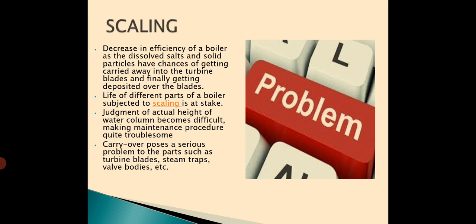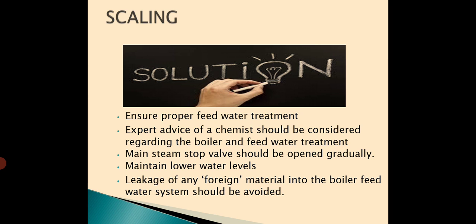Let us see the solution for scaling. First, we have to ensure proper feed water treatment and also go for expert advice of a chemist regarding the boiler and feed water treatment. We have to maintain lower water levels and the main steam stop valve should be opened very gradually. The leakage of any foreign material into the boiler feed water system should be avoided. In the initial stage, if you are able to find out the presence of scales inside the boiler, you may remove it by acid washing or using a wire brush or a scrubber or by using thermal shocks. These are some of the removal methods.